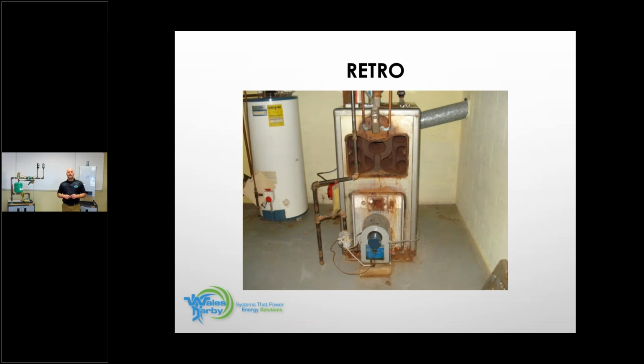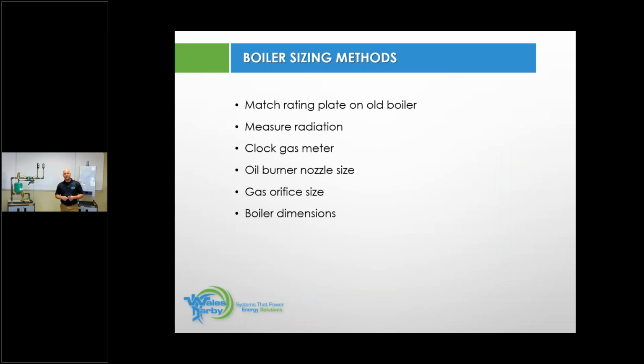Here it is, the old cast iron. Probably started out its life as an oil burner, ended up its life as a gas burner, and you're there ready to do a retro replacement on this job. So what do you need to know? It's really good to know if there's a rating plate on the boiler. If there is, take that rating plate. This way you have one gauge as to the boiler sizing.